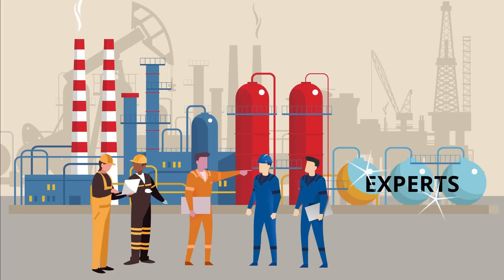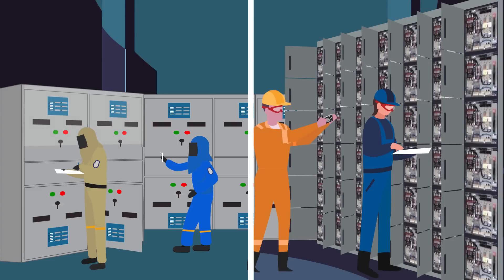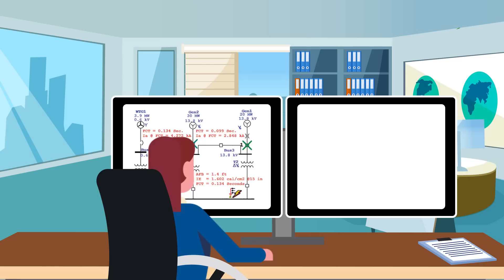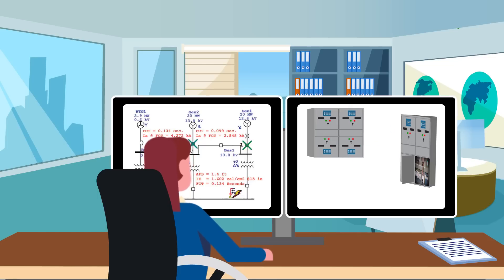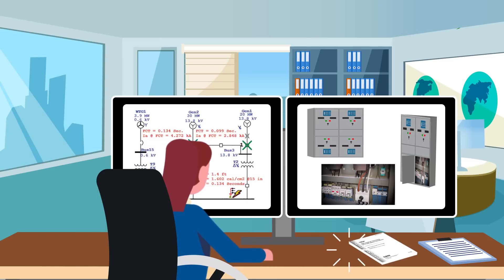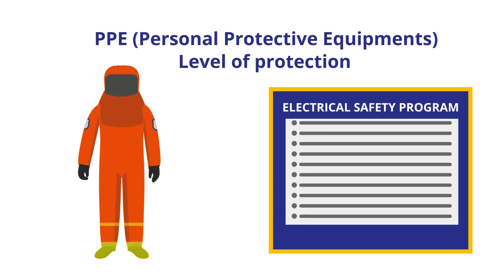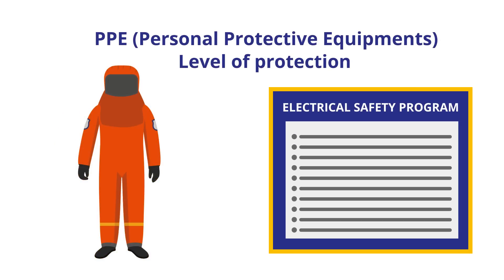Document field verification with as many photos as possible for future reference. Next, develop a power systems model using field verification data and perform an arc flash assessment using IEEE 1584 or NFPA 70E guidelines to determine worst-case incident energy levels.